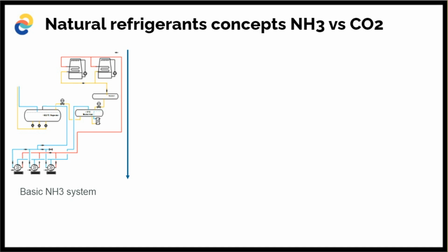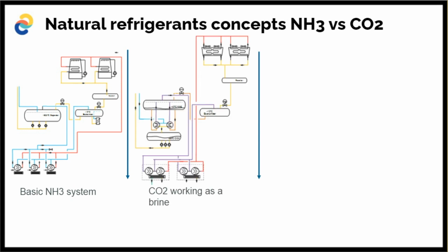So then we have to look to another system, and this is a very safe and robust system, CO2 working as an evaporating brine. It gets a little bit more complicated because you have some extra condensers and cascade condensers here. It's a bit more expensive. But here you will have only ammonia compressors in the machine room, with underneath a pump system here that pumps CO2 to the coolers and it returns back again.